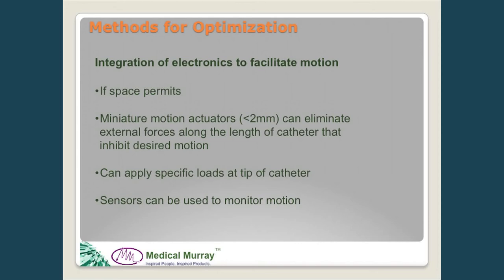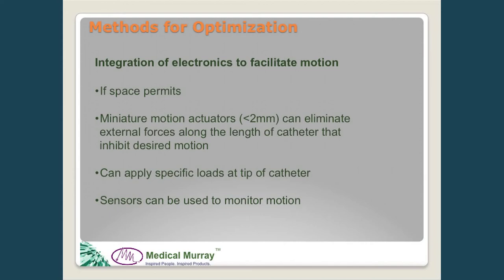This next approach is kind of the 'cheating' slide — if space permits in the device, we can bypass all the factors involved with friction and length changes by using electronics at the tip of the catheter to facilitate the needed motion. Motion actuators are available under two millimeters in size that can be installed in the distal tip of a device, so all of the motion is relative to the tip rather than the handle, eliminating the stack-up from all those variables. These actuators can apply a specific load at the tip or create motion to advance a component a specified distance.